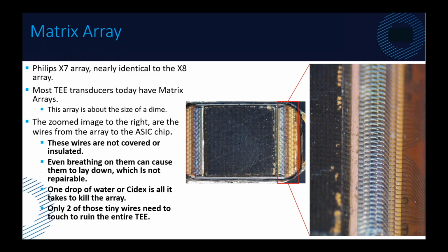If we go back 20, 25 years, and I've been in this a long time, TEE probes used to be much bigger. The array was bigger, and there was more room inside there. So manufacturers actually built waterproofing into the tip of their TEE probe, so if water got in there, it couldn't get to the array. Well, when you're that small, there's no room. You can't waterproof it, at least that's the theory.